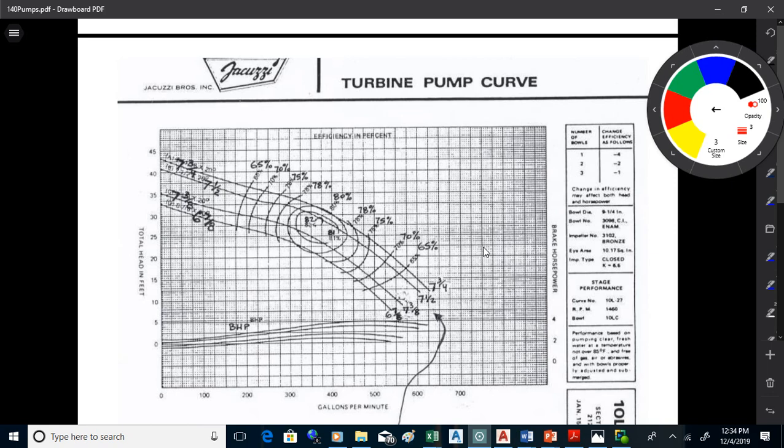Okay. Read that over this way till you hit the top curve and then read it down. I think, anyway, yeah, I'm hitting that about right. Is that what yours says? It says 7 3/4 impeller, TDH of 25? Right. So about what flow do we have there? About 480 gallons per minute, okay.